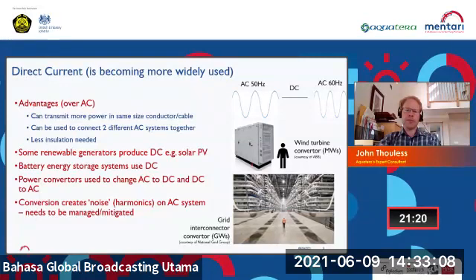The other big benefit is that we can use it to link two systems. If we've got two countries operating at different frequencies, or not in phase with each other, say one country's at 50 hertz and one at 60 hertz, we can tie those two countries together with DC and change the power between them without having to synchronize them, or synchronize two big generators.